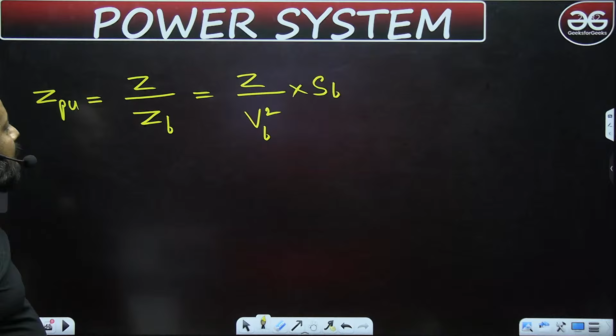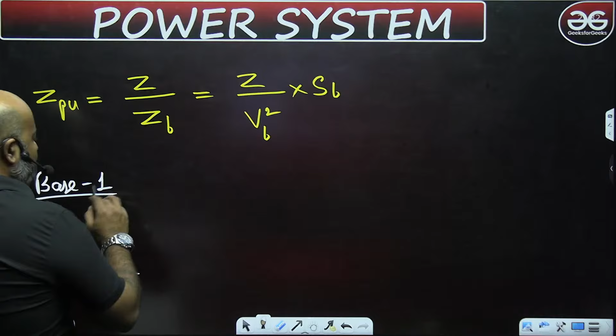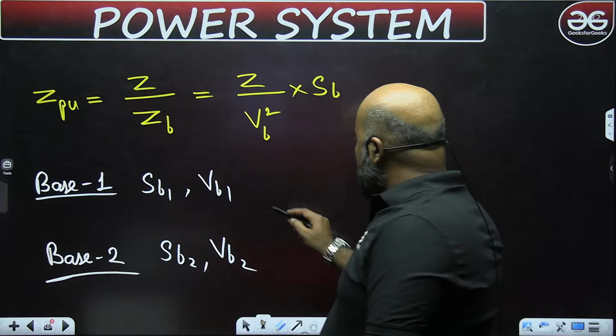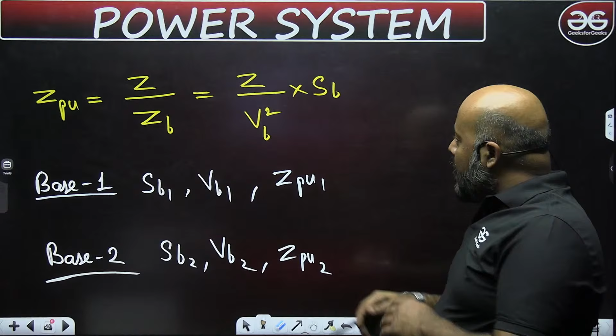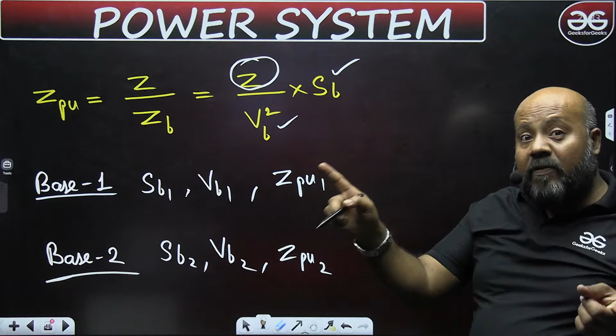Now suppose you have two different systems — base 1 system and base 2 system. Suppose SB1 and VB1 are the power and voltage base for one system, and SB2 and VB2 are the power and voltage base for the other system. Suppose the per unit value of impedance is Z per unit 1 in the first and Z per unit 2 in the second. How do you relate them? Whether it is base 1 or base 2, the actual value of impedance is not changing — it is a constant. So what is changing? The base power and base voltage are changing for the two different base systems.